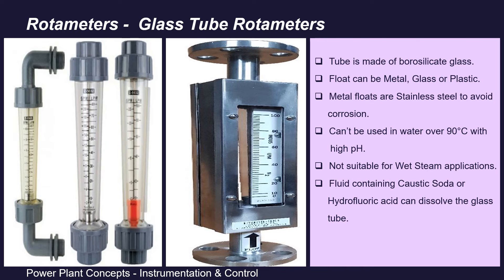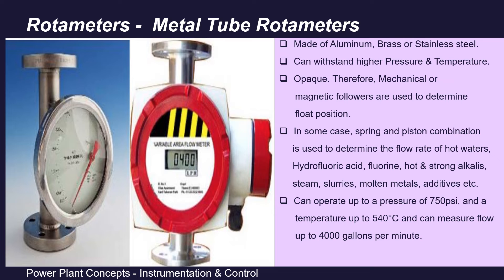The second type is metal tube rotameters. Here the tube is made up of aluminum, brass, or stainless steel. Since all these tubes are opaque, they can be used for high temperature and pressure applications. Since the tube is not transparent, the float is not visible directly for flow indication, so mechanical or magnetic followers are used to determine the float position. In some cases, a spring and piston combination is used to determine the flow rate of hot water.